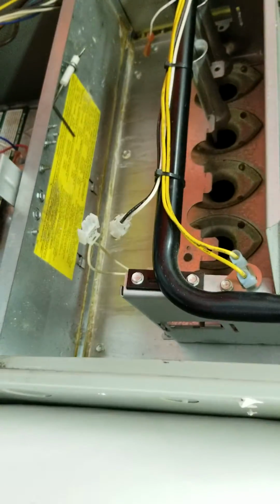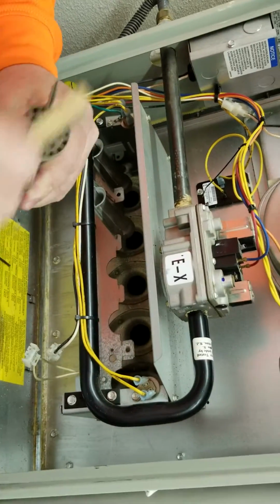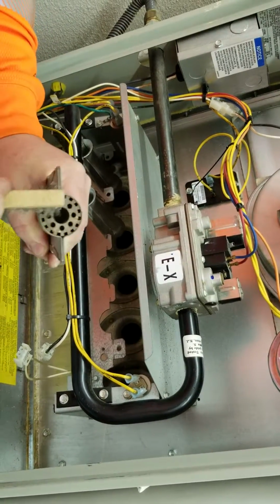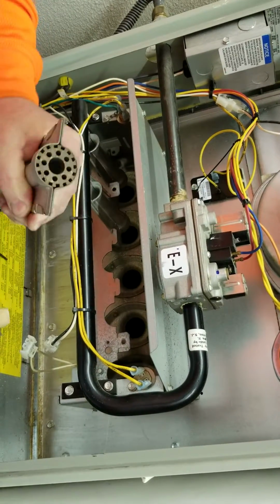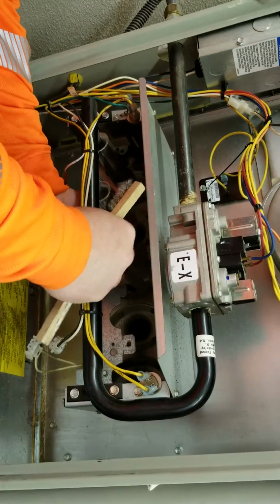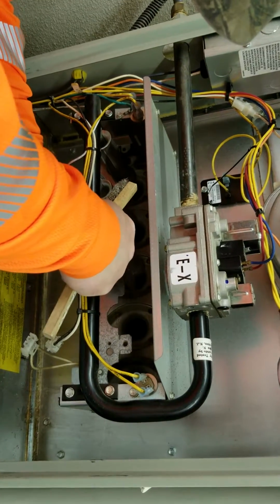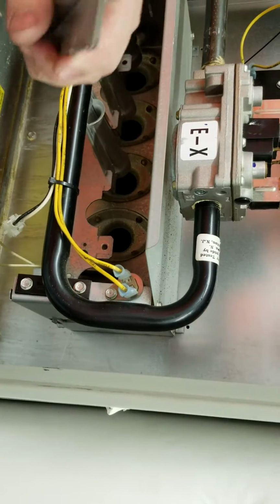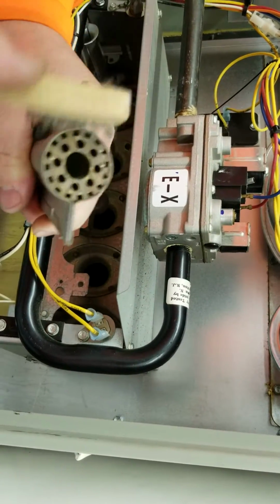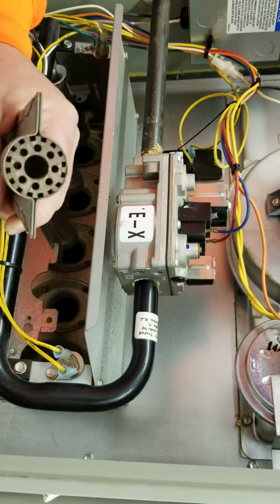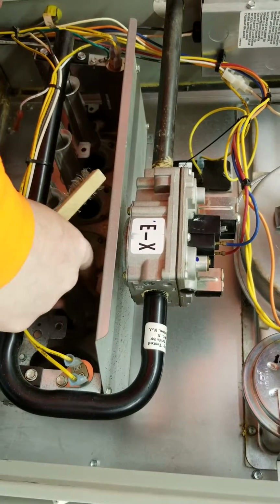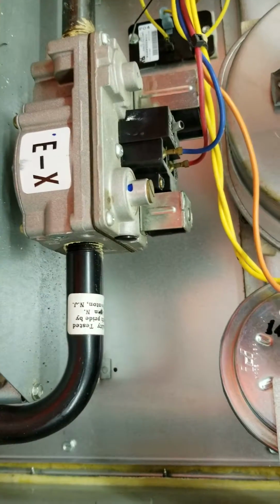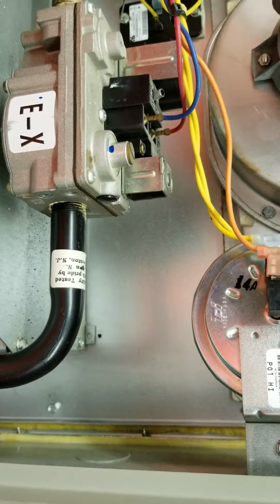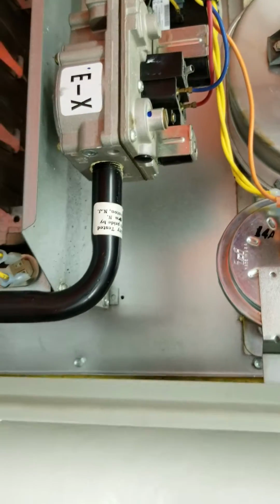So that's 2, so go ahead there again. And that'll be 3. Again, sometimes they get a little tricky to get them in and out of there, but you may have to bend on it just slightly on the rail that those burners set on to get them in. But again, make sure that they're clean. The burners themselves are clean. That's also part of the path for sensor current.